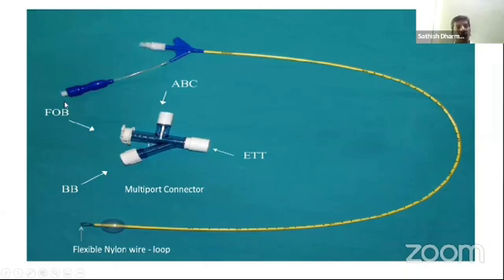It has a pilot catheter to inflate the balloon, and a multi-port connector with an endotracheal tube connection, a bronchial blocker insertion port, a fiber optic bronchoscope insertion port, along with the circuit connection port. So we should know all these ports, because we should connect the system appropriately in the respective places.